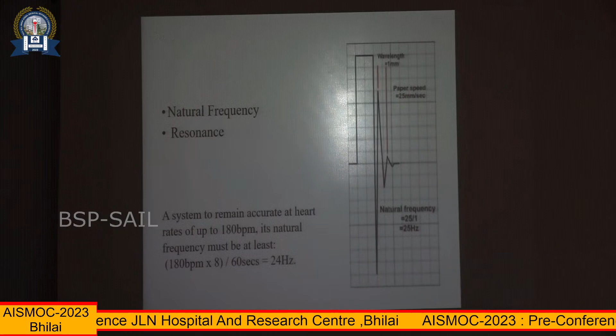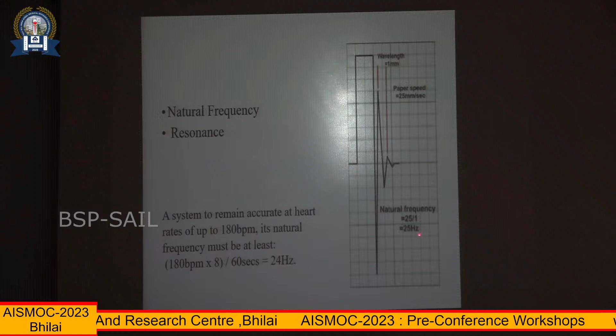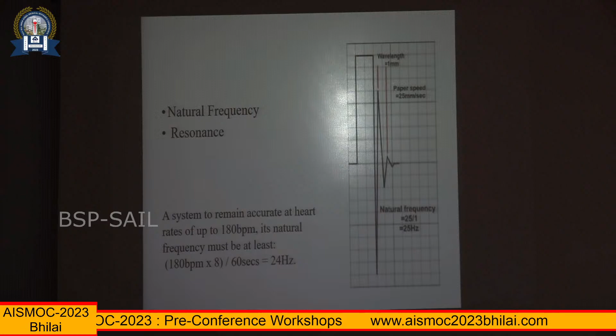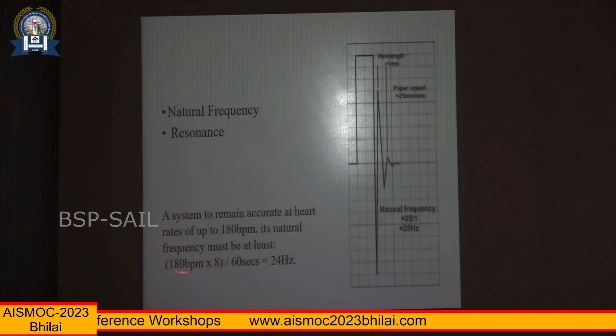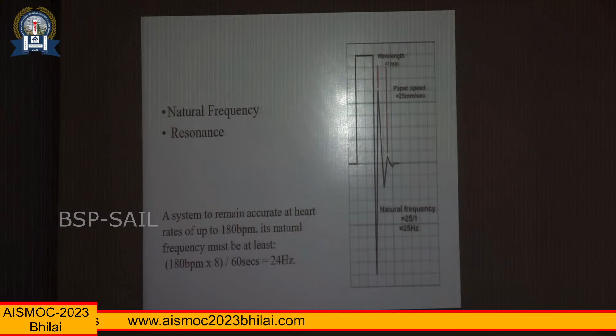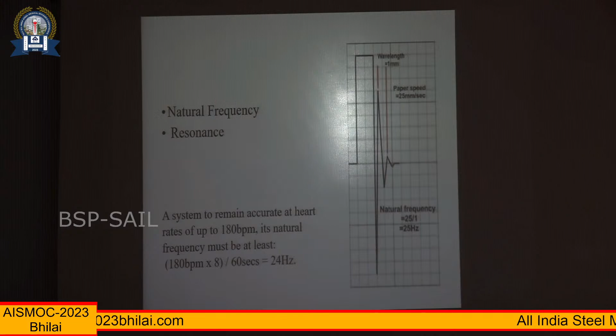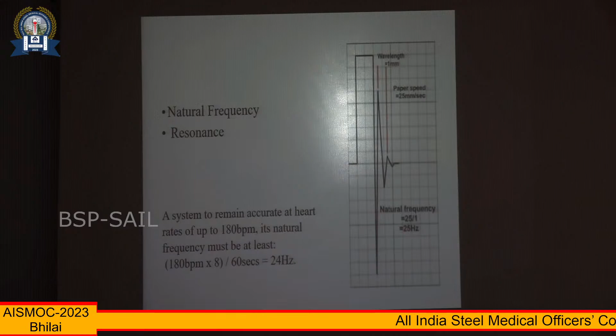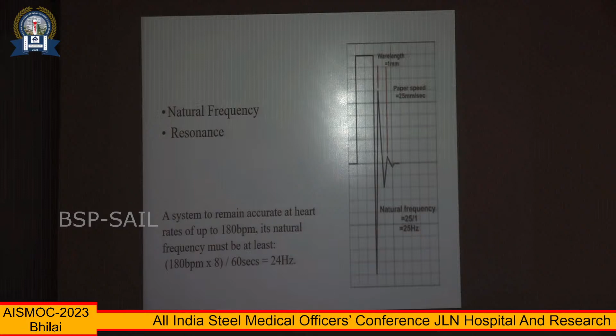So see, for example, now in this system, the natural frequency of the system is 25 hertz. So the system is reliable even if the heart rate is 180, because as I said, of the first 8 harmonics, most of the information is in the first harmonic. So the transducer will take 8 harmonics. Okay, so if the heart rate is 180, or the fundamental frequency is 180, and the total number of harmonics considered by the transducer is 8, you will get a frequency of 24. So the frequency of the transducer is 25, so it can still reliably give you the blood pressure even if the heart rate reaches 180. Got it? Okay, great. So once this concept is clear, I think the arterial system is pretty much done.